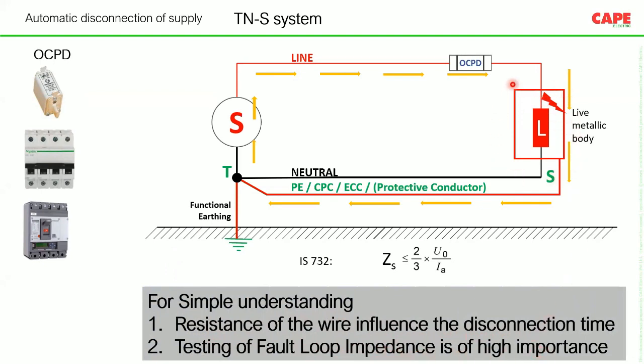Now I am moving the cursor in the location, live metallic body. It is connected to the neutral of the transformer through a metallic connection, a metallic conductor. So the exposed conductive parts or the extraneous conductive parts are finally connected to the neutral of the transformer through a metallic connection, and this metallic protective conductor must run along with the phase and the neutral conductor. Don't try to route it through a different route. So there are some rules which have to be followed here.